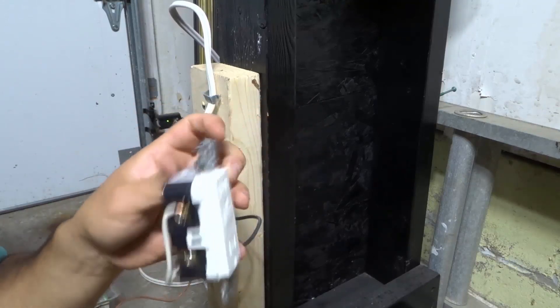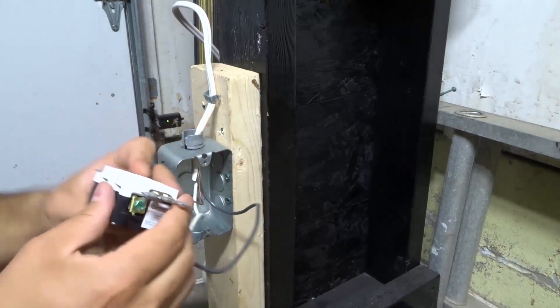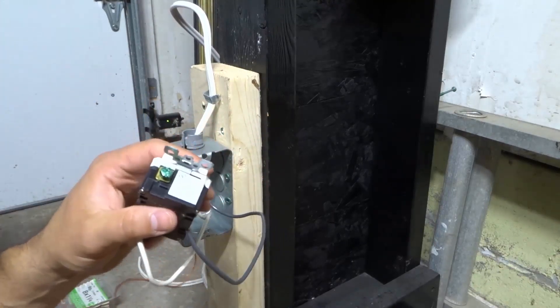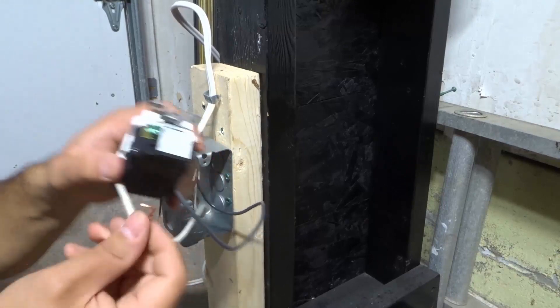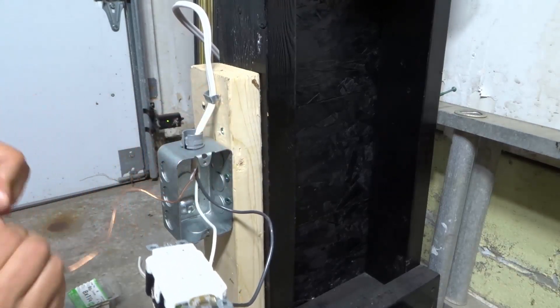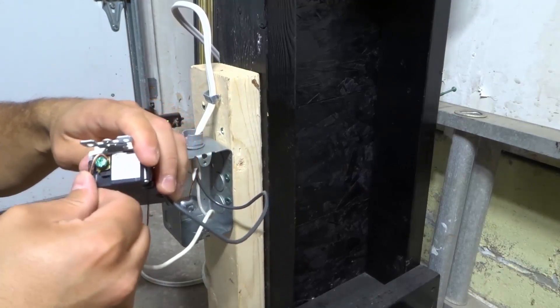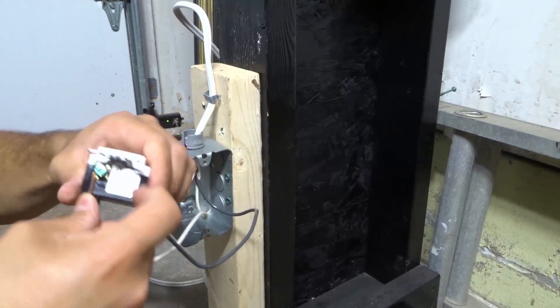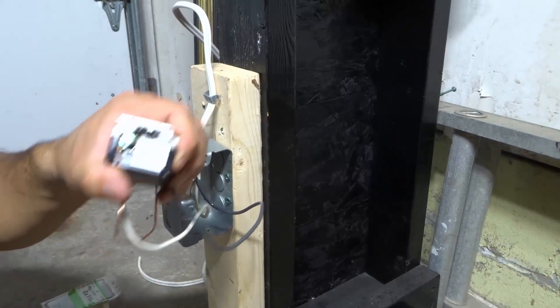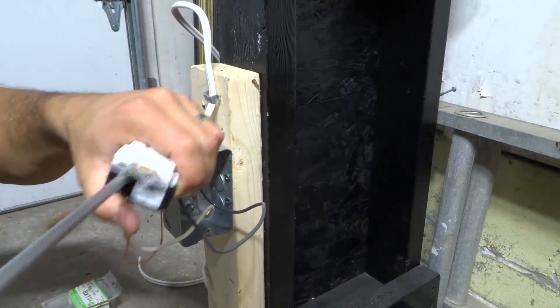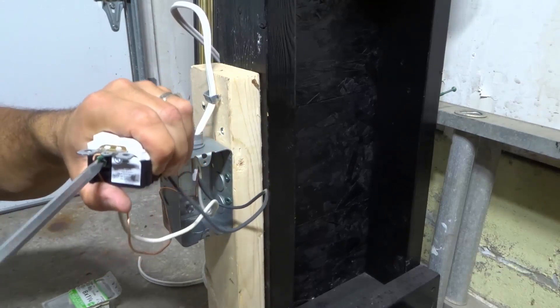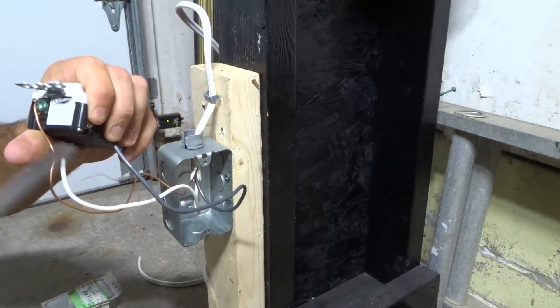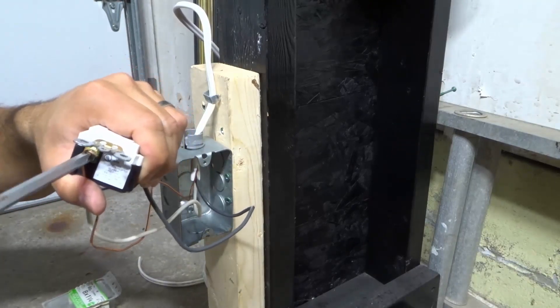Next up, we take our ground screw, which is down here at the bottom. It's already loose in this case. We're going to hook this around, once again making sure that your loop is in the same direction as the tightening of your screw. Just get your ground wire on that green screw—the bare copper wire—and tighten it down nicely. Make sure it's nice and tight. In this case, the loop wasn't good enough; you see that ground wire just came out.